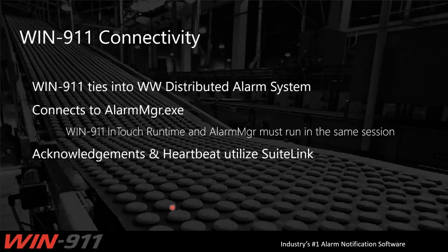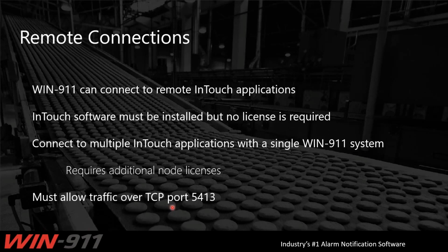And so also when it comes to acknowledgements and heartbeats, it utilizes the SuiteLink part of it, which is a service that runs alongside with the alarm MGR process. We can connect remotely to InTouch applications. However, the InTouch software must be installed on the same machine as where Win911 is installed.